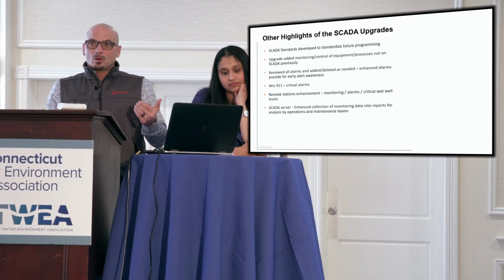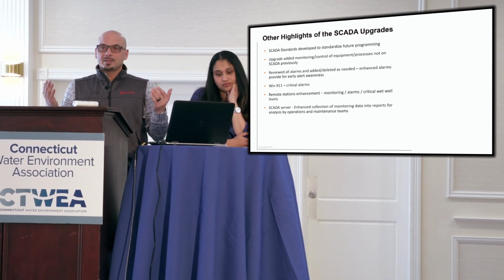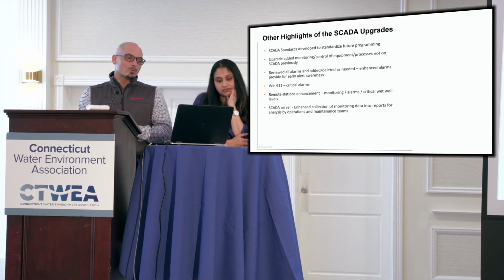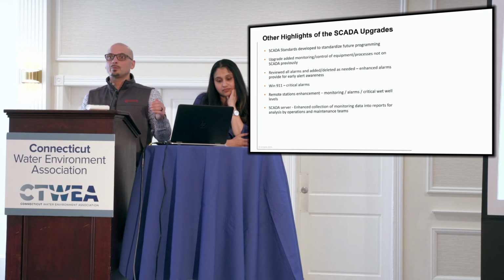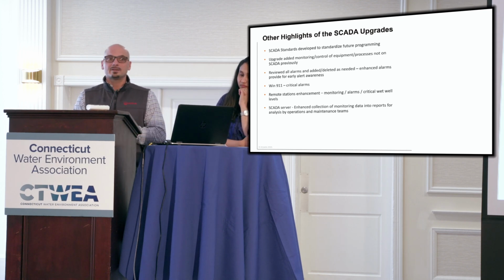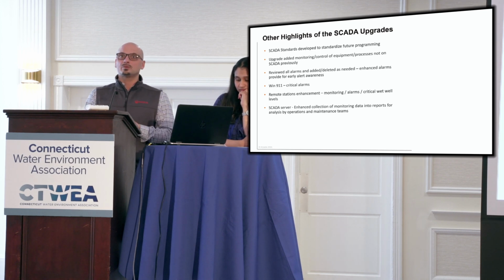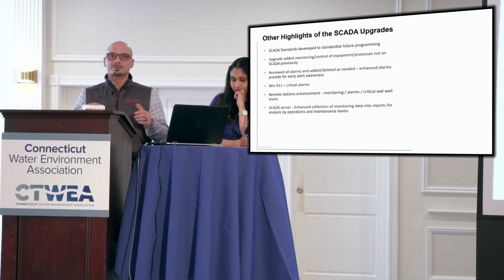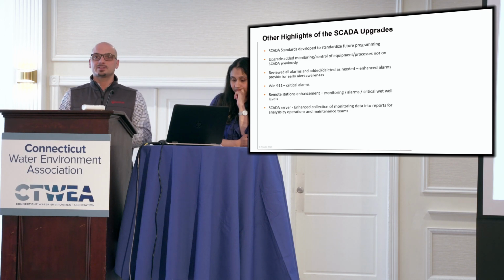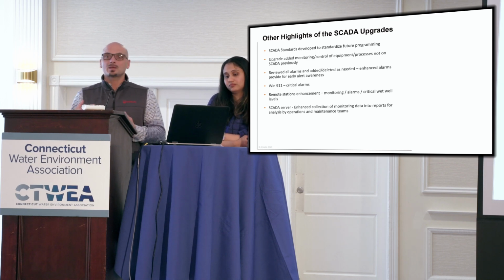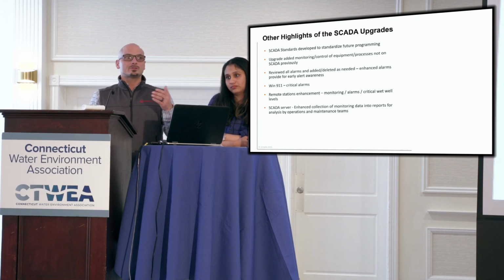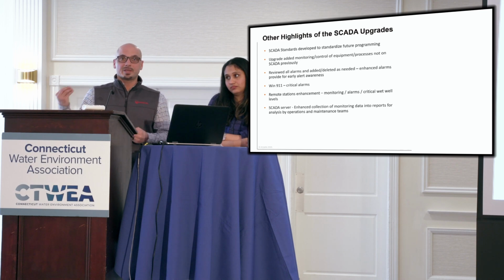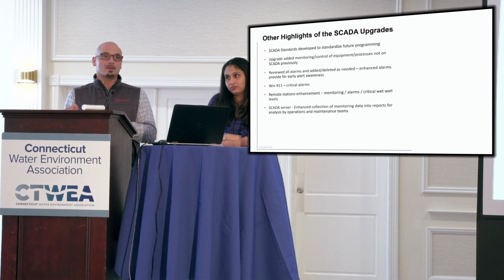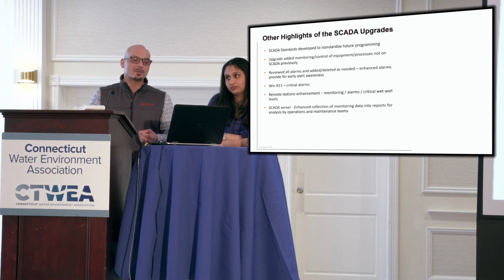We can review all the alarms going back as many days as we want, and then there's Win 911, which handles critical alarms. It's attached to SCADA, so if we get a high level at a pump station, or a pump shuts off, that's very critical - we'll get an email or a text message, because sometimes an operator is out taking DOs and won't be in front of the screen to see the alarm come in. It'll ring on their phone and they'll be able to address it immediately.